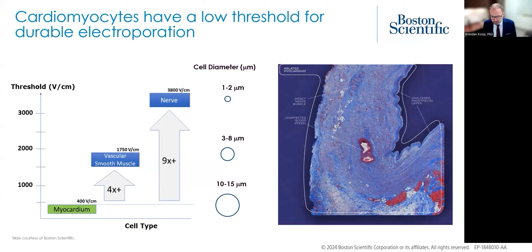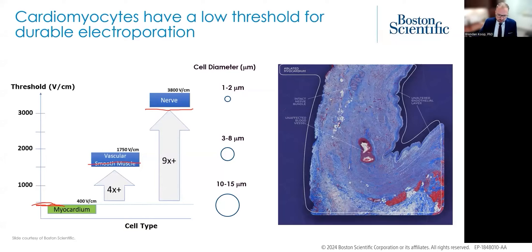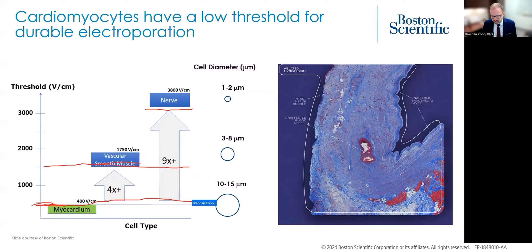Because of these two key points for cardiomyocytes, the cardiac cell has the lowest threshold for irreversible electroporation of any of the cells that we're trying to treat — around 400 to 500 volts per centimeter, depending on the waveform and catheter design. The other types of tissue in the area — vascular smooth muscle, endothelial cells, nerve cells — have many multiples higher threshold for irreversible electroporation. So our job as designers is to treat the local tissue with electric fields in this range, sparing tissues we don't want to ablate while ablating the cardiomyocytes we are trying to ablate.